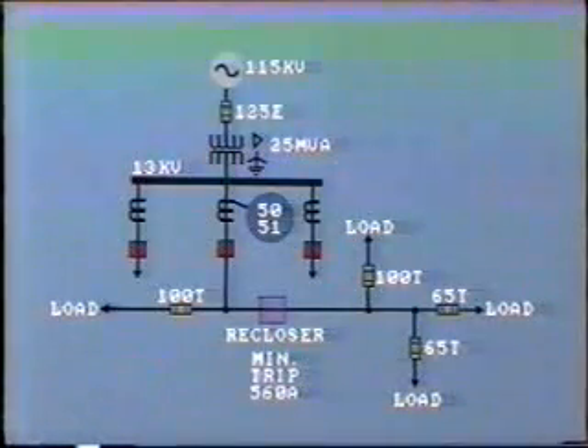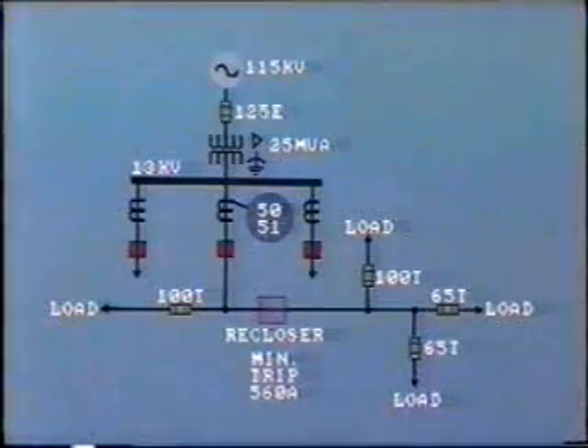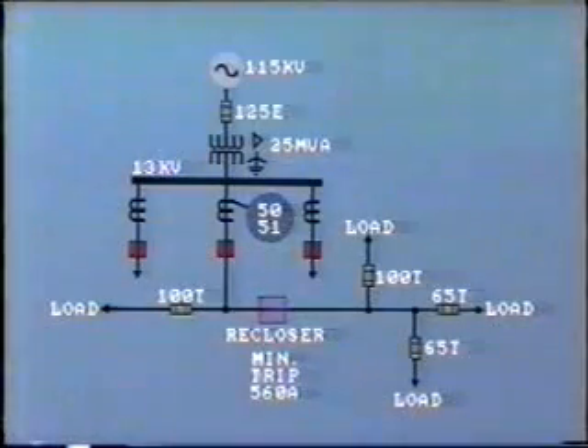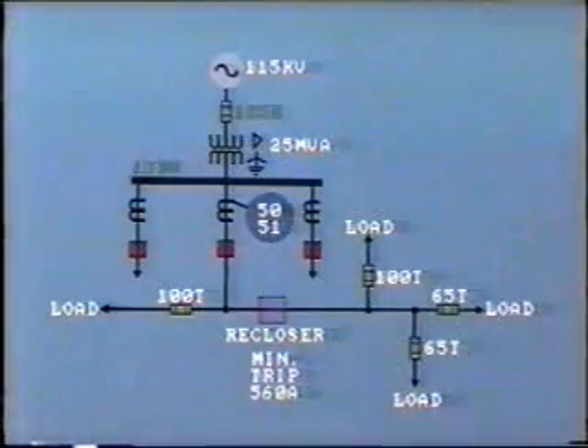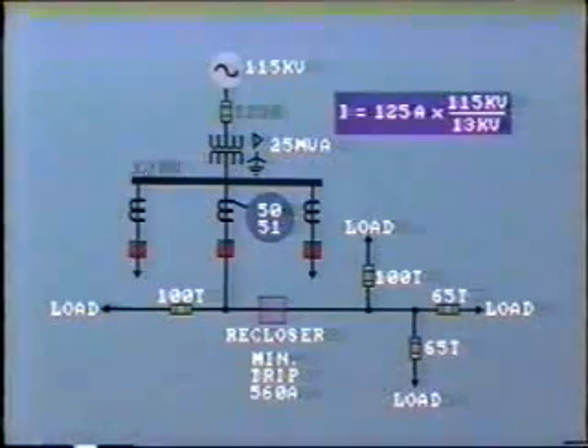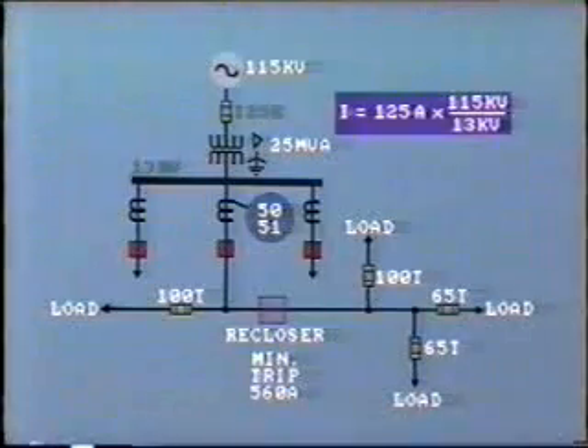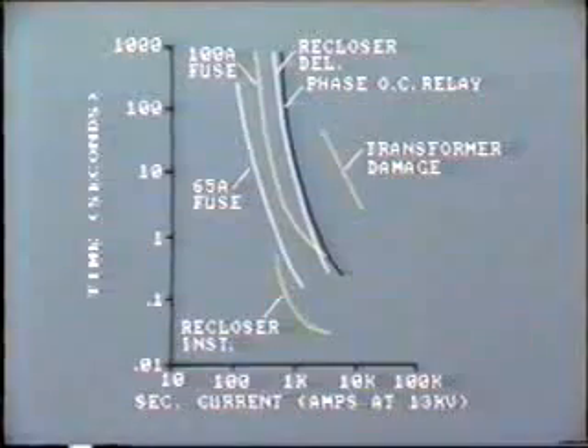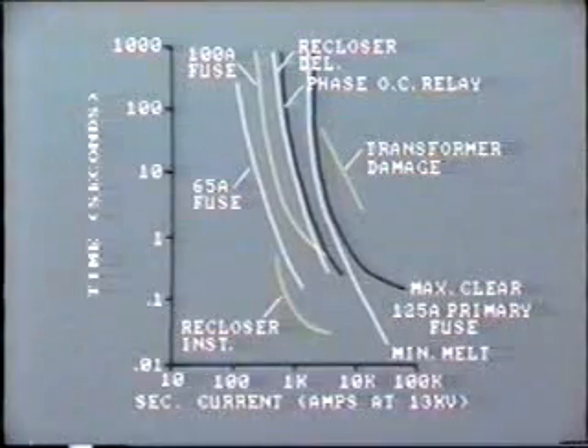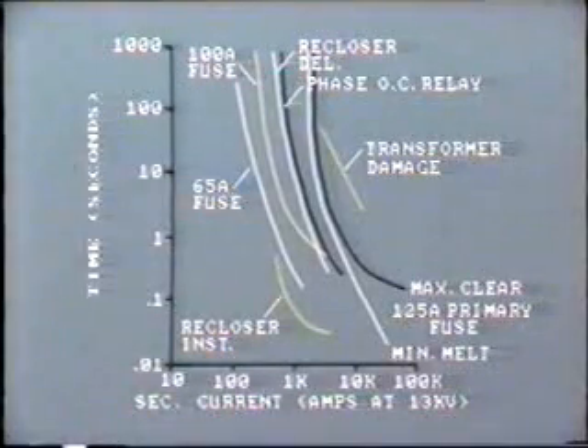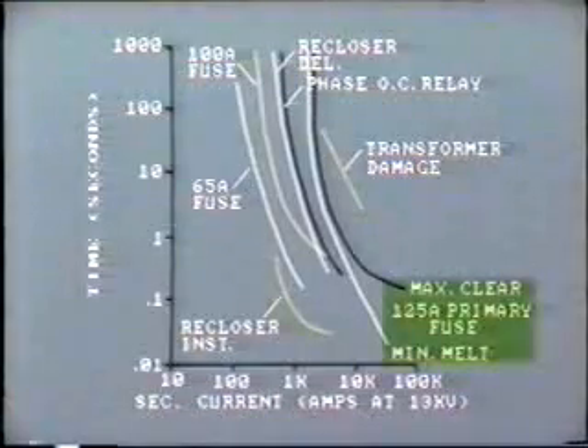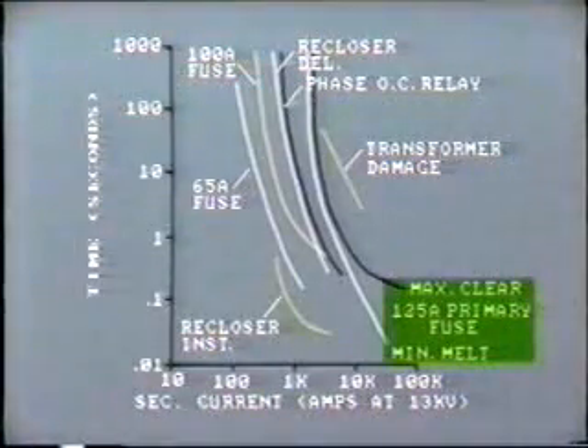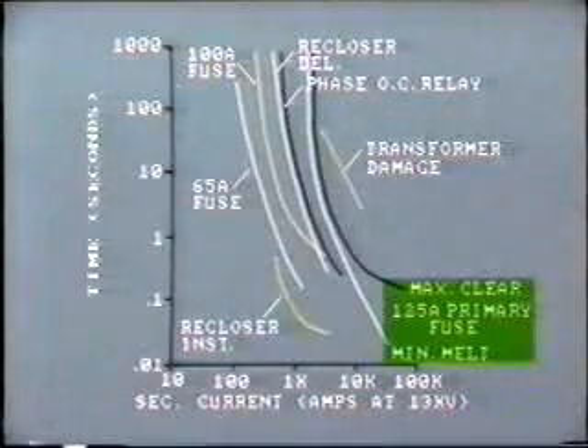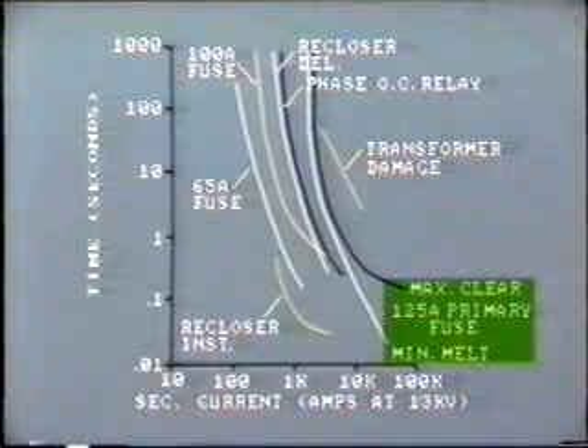In order to compare the primary fuse characteristics with the other protection devices, we must convert the primary current into secondary values at 13 kV. Each current value must be multiplied by 115 kV and divided by 13 kV. The characteristic is shown here on the curve. Once again, good coordination is provided. The high voltage fuse protects the transformer, but it will only operate if the downstream devices fail to clear the fault.